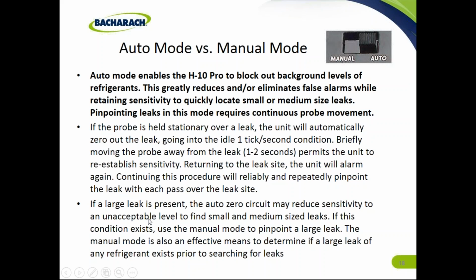If a large leak is present, the auto zero circuit may reduce sensitivity to an unacceptable level to find small and medium-sized leaks. If this condition exists, use the manual mode to pinpoint a large leak. The manual mode is also an effective means to determine if a large leak of any refrigerant exists prior to searching for leaks.